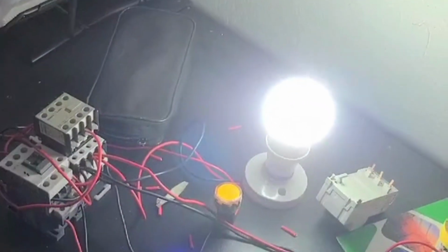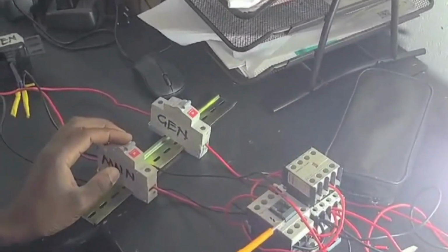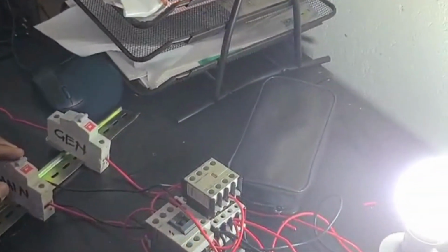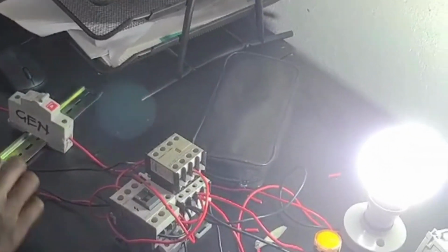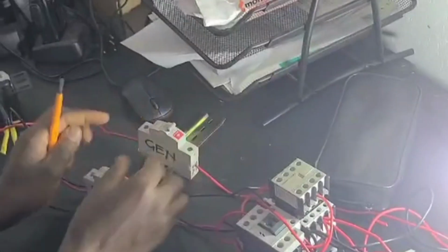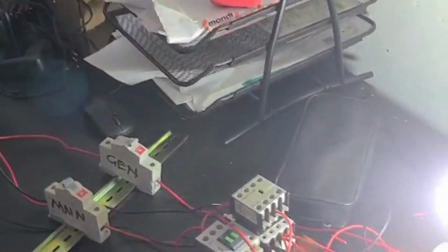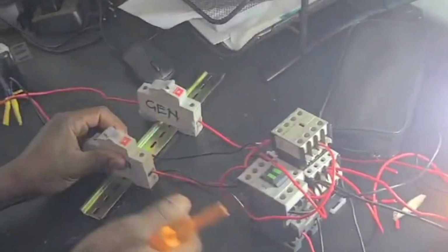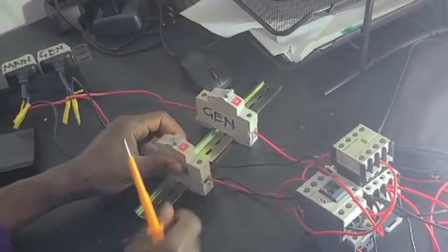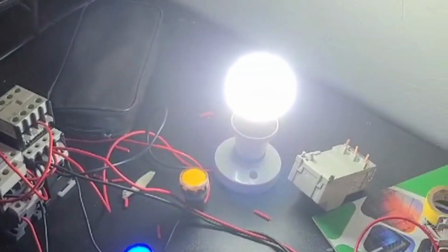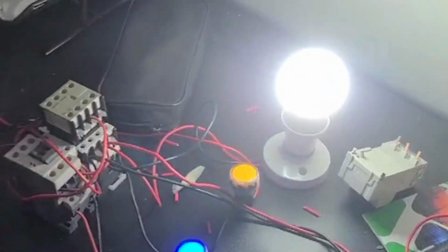But in a scenario where we have both generator and mains at the same time, we made this mains contactor our priority, so that at the time where we have both on, the load should be using our mains power. Just briefly, as you can see, if generator is off, mains work. So once mains is off, the circuit switches to generator. But once mains comes back, if the source is restored, then the system automatically switches to mains and leaves the generator alone.